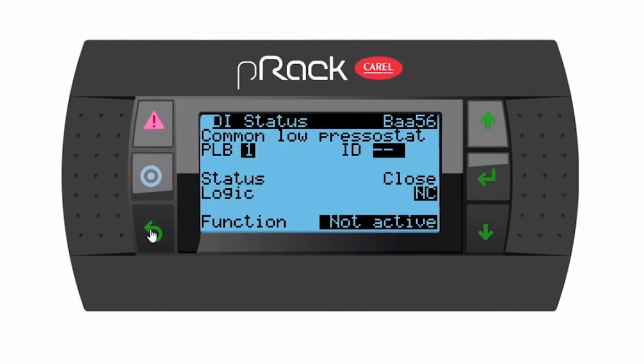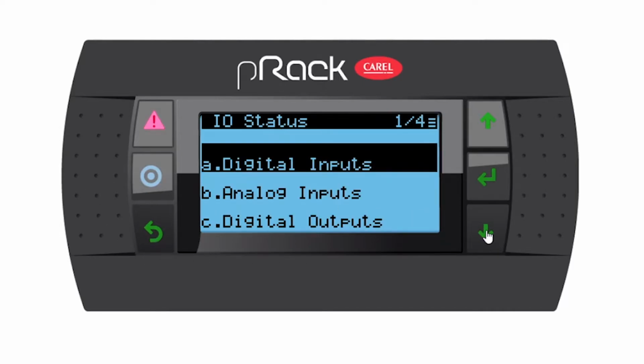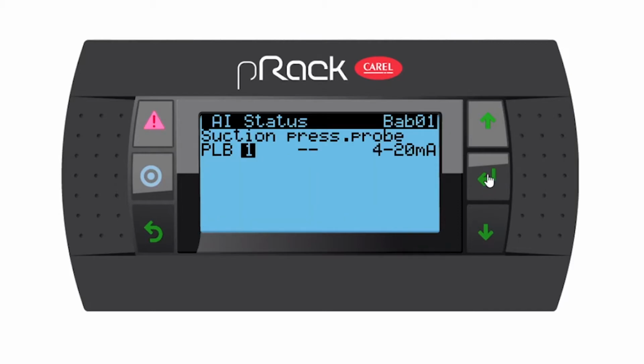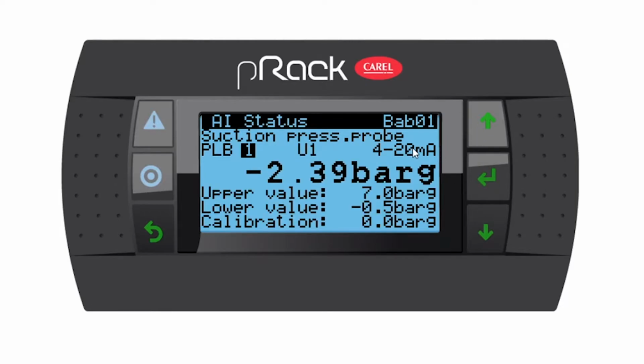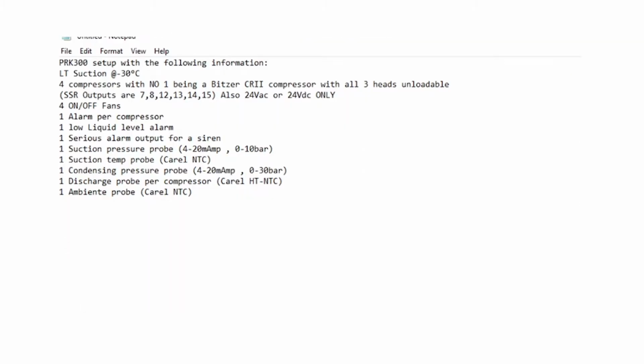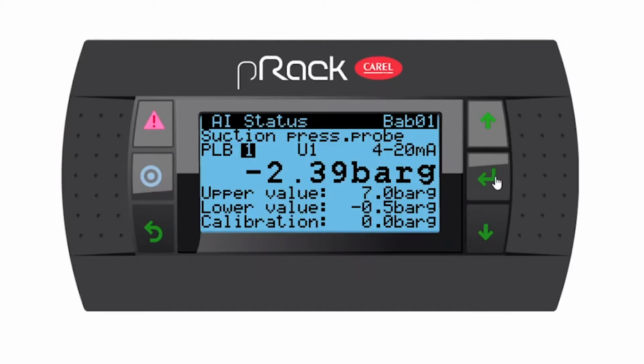So we're going to escape from this menu and go to analog inputs and enter. Suction pressure probe. Yes, we do have one. I'm going to assign it to U1. Yes, it's a 4 to 20 milliamp. But remember, my note said it's a 0 to 10 bar. So let's change the range to 0 to 10.